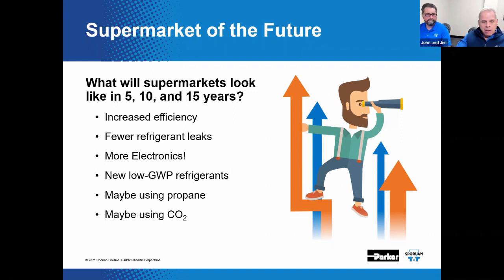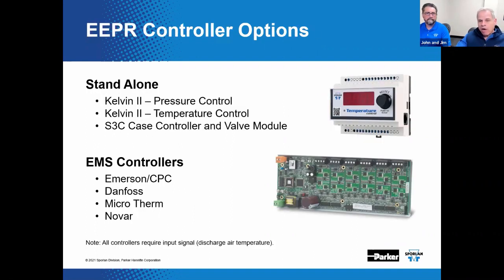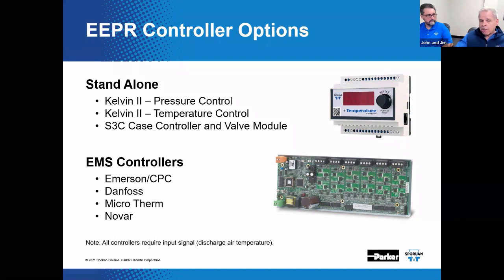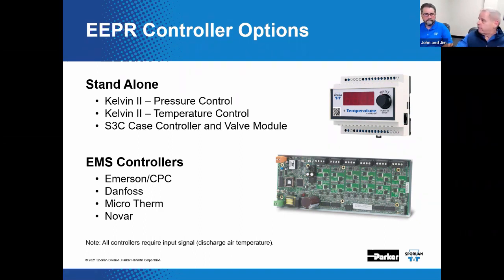Yeah, exactly. Regarding controllers and electronics, we offer a standalone controller to drive an electrically actuated, electronically controlled EPR. Here are some examples. The temperature control and the pressure control out of the Kelvin lineup, and they are also case controls that can operate as standalone devices. More commonly, an EEPR would be controlled by a dedicated board or case control that could communicate with the store's EMS or BAS. That's the energy management system or the building automation system for the whole store. That allows the technician to see and monitor case temperature, valve position, et cetera. It also allows for even more remote monitoring to take place, from a remote location, for remote control, and that can head off failures and product loss. Absolutely.